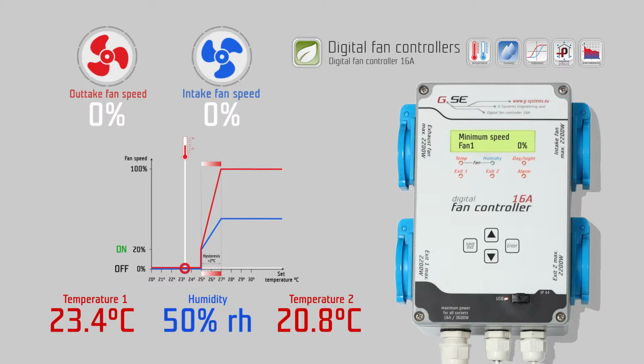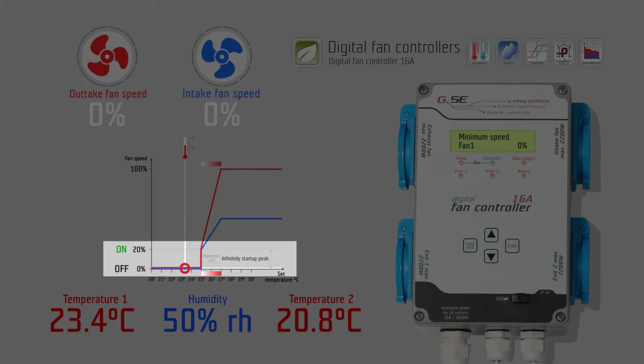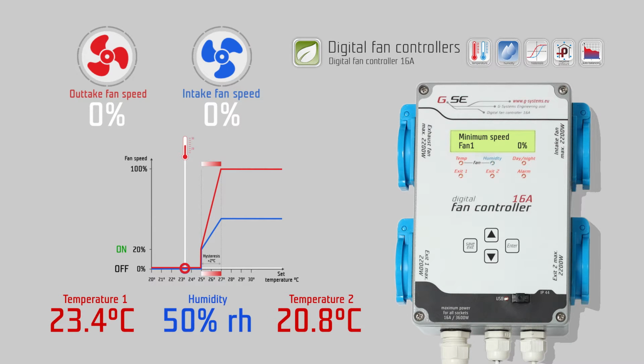The exhaust fan will stop working when the measured temperature or humidity are below their set values. The minimum speed setting has a 20% initial start-up peak, to give enough power to the fan to run on low speed. Pressing the up-down buttons will change the value, up to 100% speed. Set the desired value and press Save Exit.